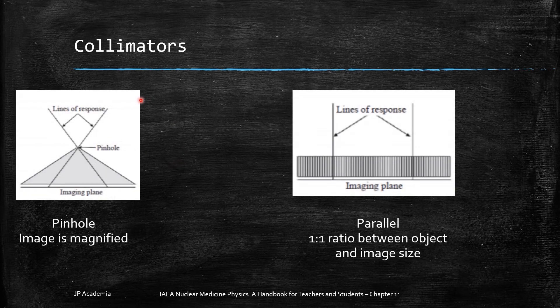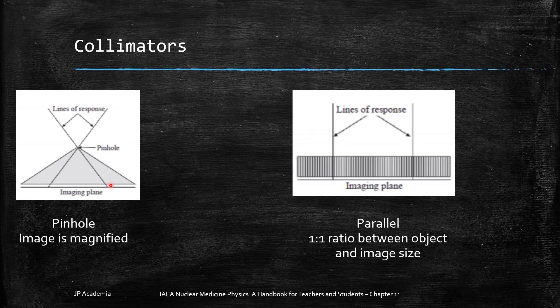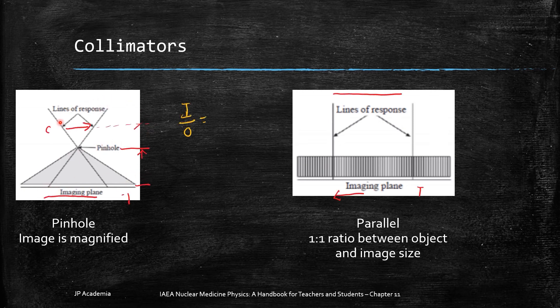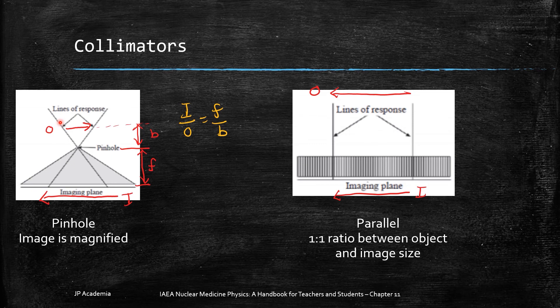First, we have the pinhole collimator. Then we have the parallel collimator. For the pinhole, the focal point is placed between the image plane and the object being imaged. We can define the image size I over the object size O, which is equal to the distance F over B. The distance F is the distance from the pinhole to the image plane and B is the distance from the object to the pinhole.